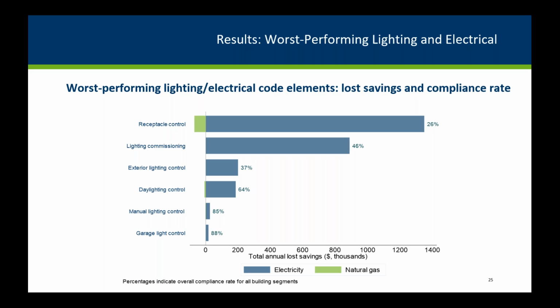I won't spend as much time on our lighting and electrical code elements, except to point out here that all of the code elements that we saw with significant lost savings involved controls or commissioning. Receptacle control was one of the least compliant electrical code elements and applicable to half of the buildings in the study. ASHRAE 90.1 2010 requires at least 50% of all receptacles installed in private offices, open offices, and computer classrooms be controlled by an automatic control device that functions on a schedule or occupancy sensors.